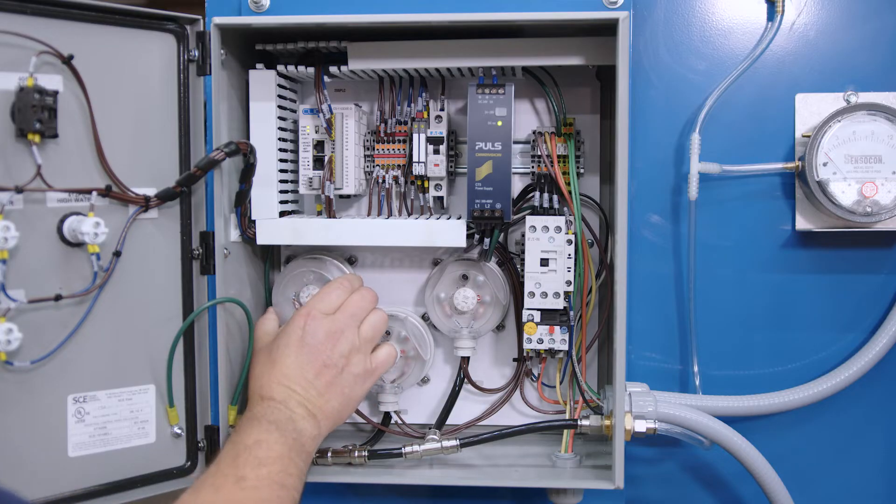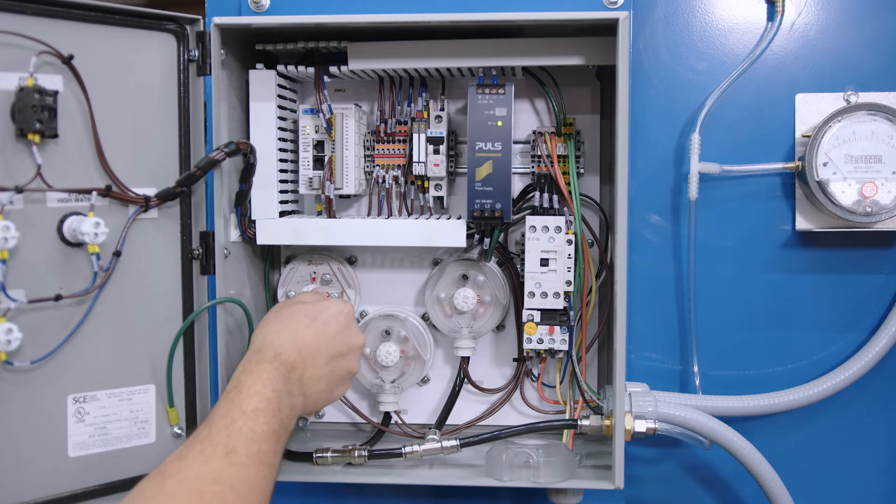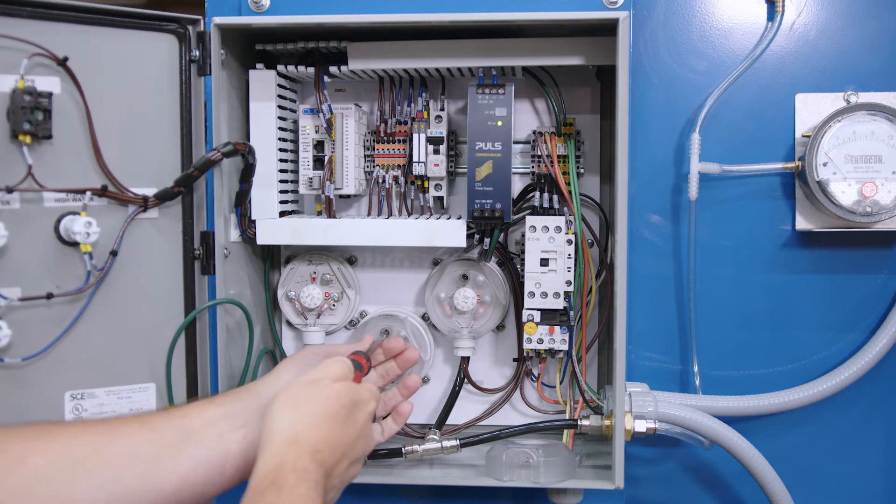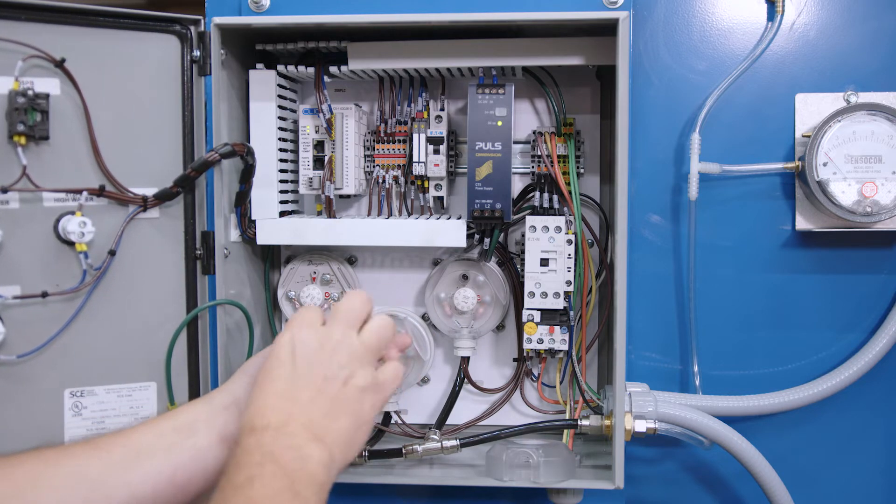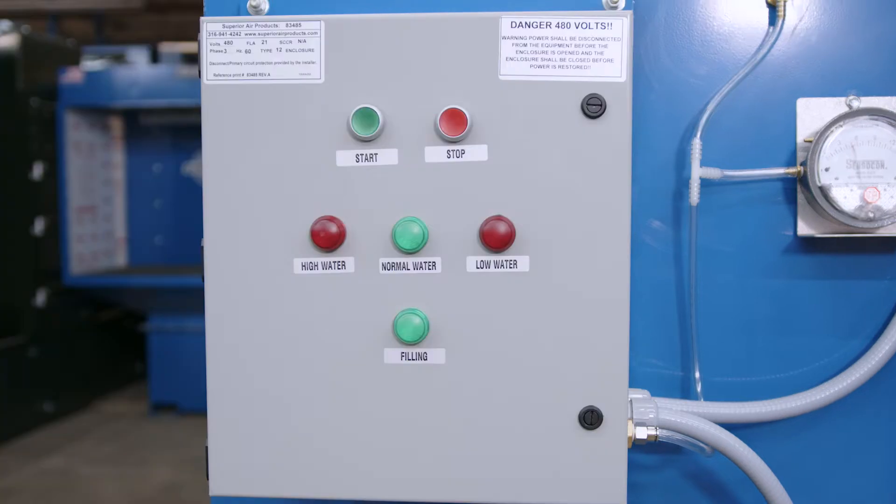The unit is controlled by a pre-programmed PLC unit and three pressure switches. The pressure switches control water levels inside the unit based on static pressure. Per NFPA and OSHA regulations, the Superior Wet Collector will automatically shut down at the low water switch setting or the high water switch setting and display a visual alarm on the control panel.